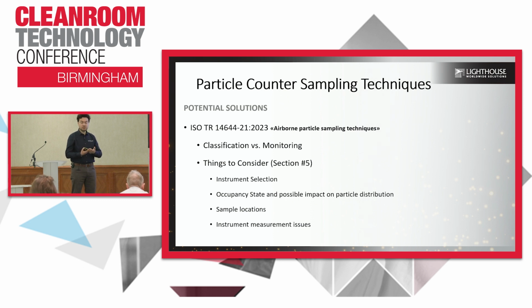In section 5, there are things to consider. One of them is the instrument selection. We know that different instruments are available in the market, so you have to know which one is the best for your application. That's number 1. Number 2, occupancy state and how you will correlate these at rest, in operation conditions and also as built conditions. So you have to define these conditions to make the necessary design. And sample locations, to select them, it has to be risk-based. But also you have to place them into the right location where you will be able to do your sample. For example, if the risk for the same location, same zone, is quite similar, then your priority will be placing your particle counter in the easiest point without having a long distance to sample. So this will be your things to consider while selecting the sample locations.